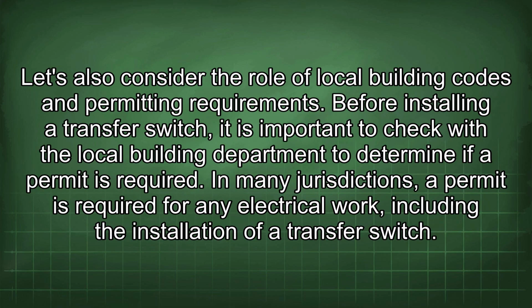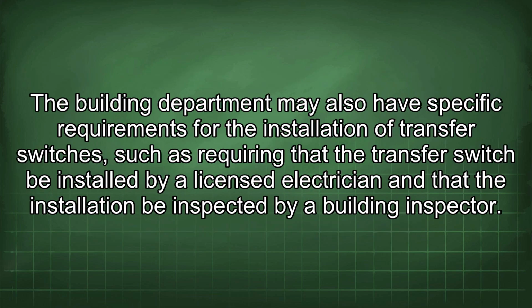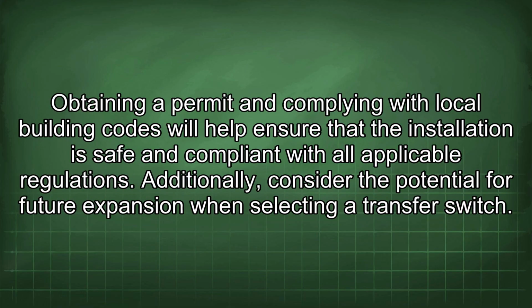Let's also consider the role of local building codes and permitting requirements. Before installing a transfer switch, it is important to check with the local building department to determine if a permit is required. In many jurisdictions, a permit is required for any electrical work, including the installation of a transfer switch. The building department may also have specific requirements, such as requiring that the transfer switch be installed by a licensed electrician and that the installation be inspected by a building inspector. Obtaining a permit and complying with local building codes will help ensure that the installation is safe and compliant with all applicable regulations.